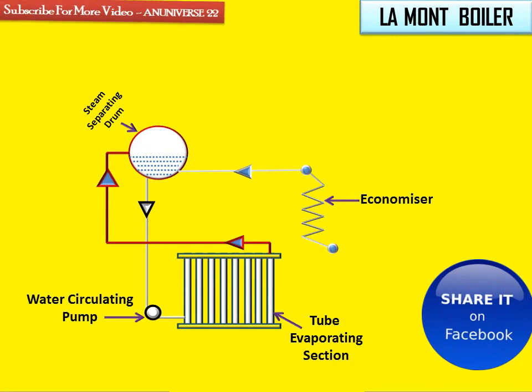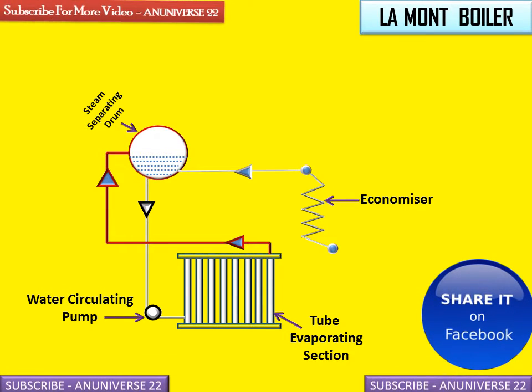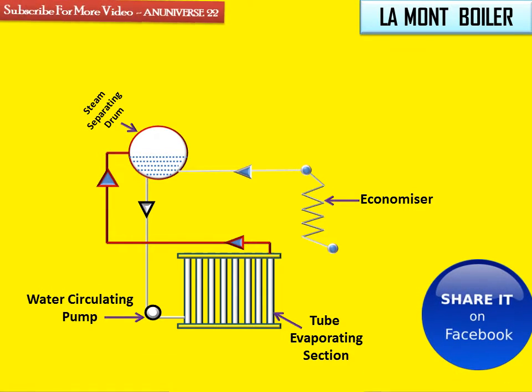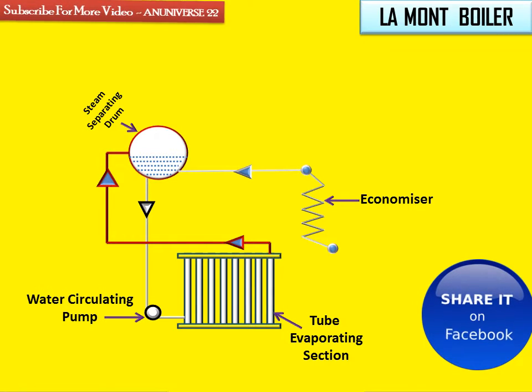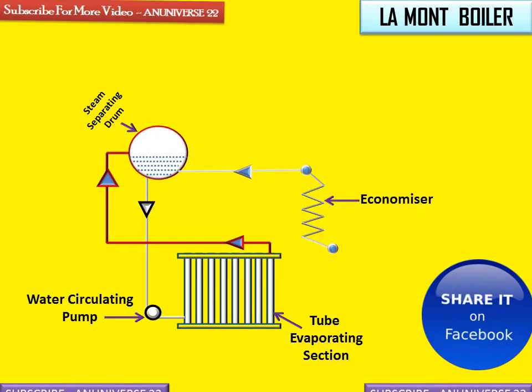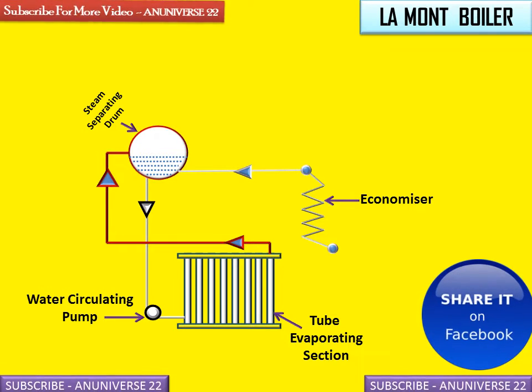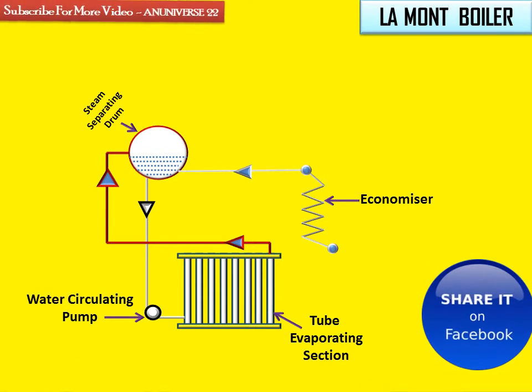This is the water circulating pump. Since the La Mont boiler is a forced convection boiler, a centrifugal pump is used to recirculate water inside the boiler. This pump is driven by the steam turbine, and the steam for the turbine is taken from the boiler itself.